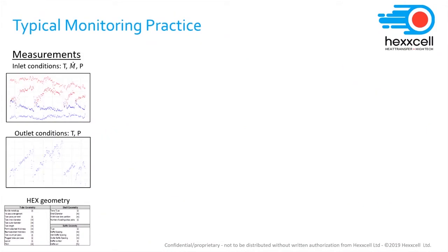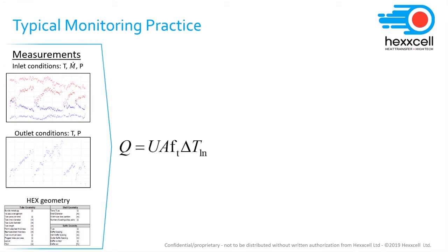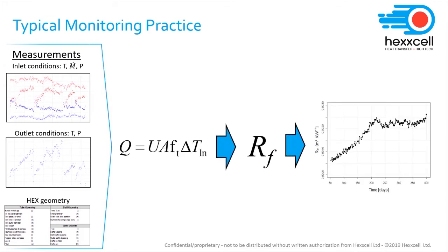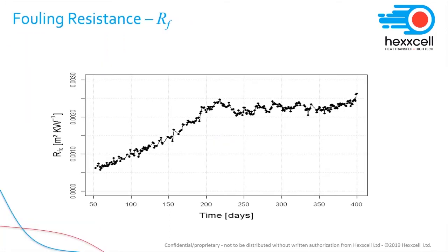From a monitoring perspective, we take the plant data, inlet and outlet conditions, and the geometry of the heat exchanger, and we calculate a fouling resistance by essentially using the same equations and the same assumptions that we have seen before for design, producing the well-known graph showing the evolution of a fouling resistance over time that I'm showing here on the right-hand side. So what are the issues with this approach?